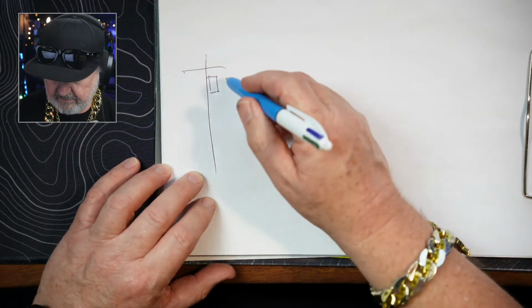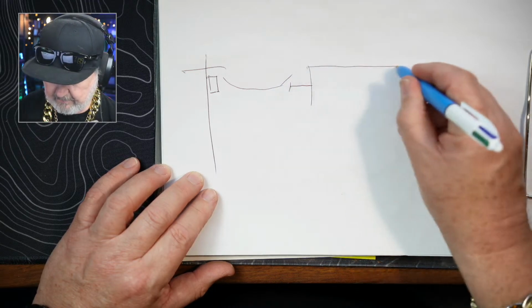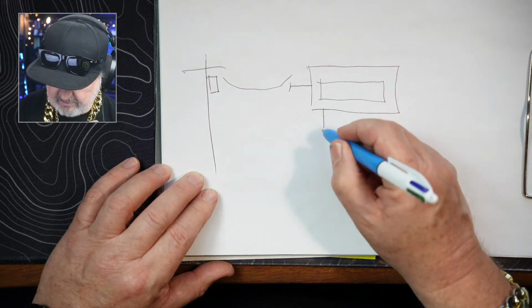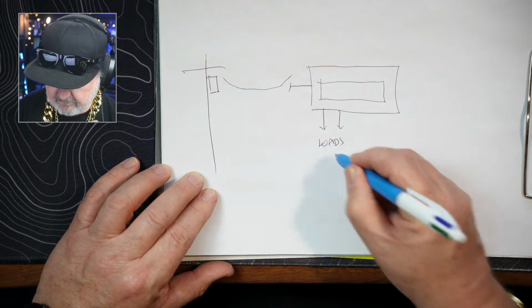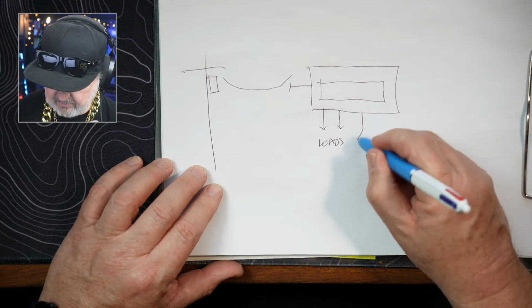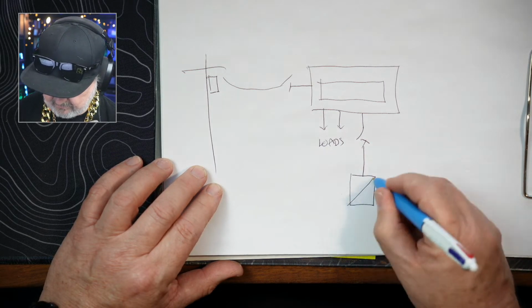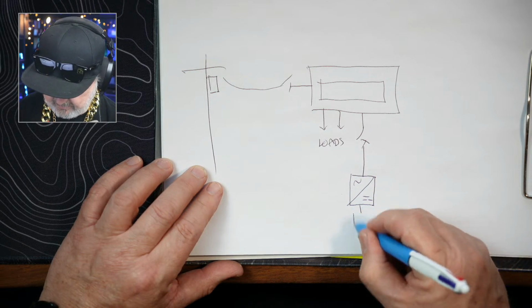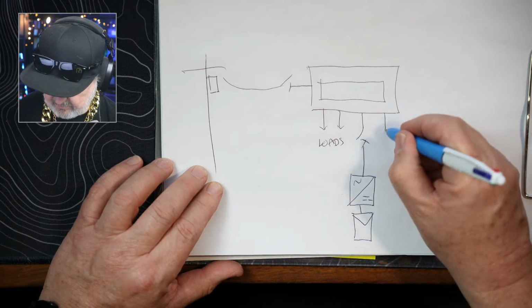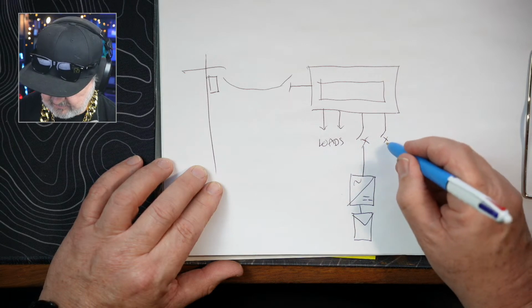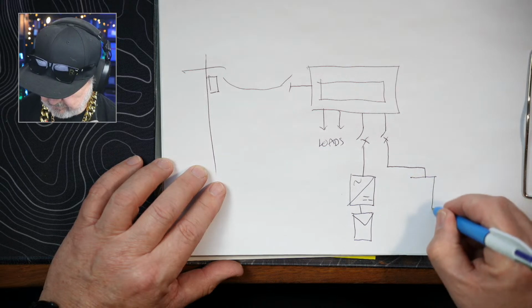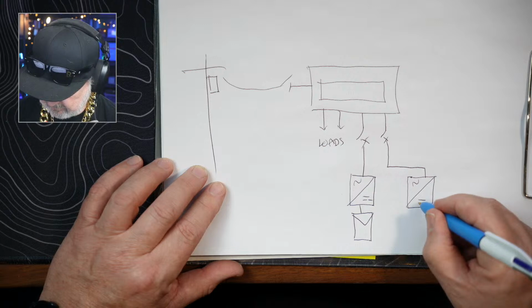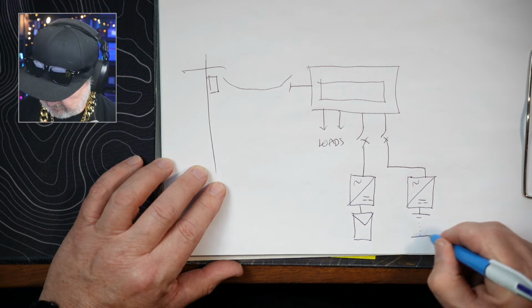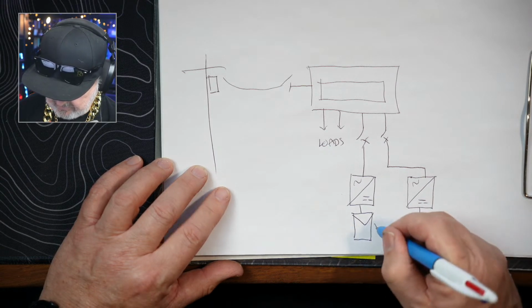Go for a fresh bit of paper here. So there's our grid supply coming in, and the main switch. There's our switchboard and some loads. Just do little arrows for loads. And now we've got two inverters. So one inverter is a solar inverter. Has solar panels connected to it. And another inverter is a battery inverter. So this is what we call AC coupled storage. So that's my battery, and that's my PV.